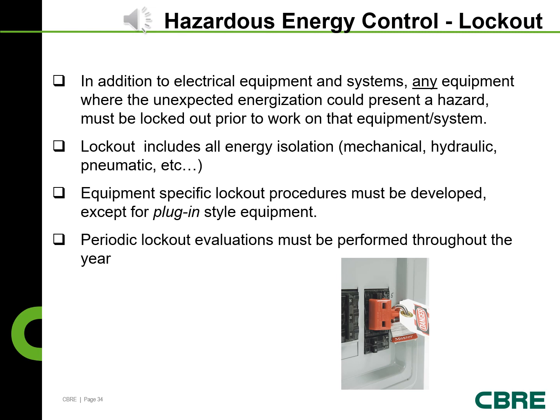Hazardous Energy Control Lockout. In addition to electrical equipment and systems, any equipment where the unexpected energization could present a hazard must be locked out prior to work on that equipment or system. Lockout includes all energy isolation, mechanical, hydraulic, pneumatic, etc. Equipment-specific lockout procedures must be developed except for plug-in style equipment. Periodic lockout evaluations must be performed throughout the year.